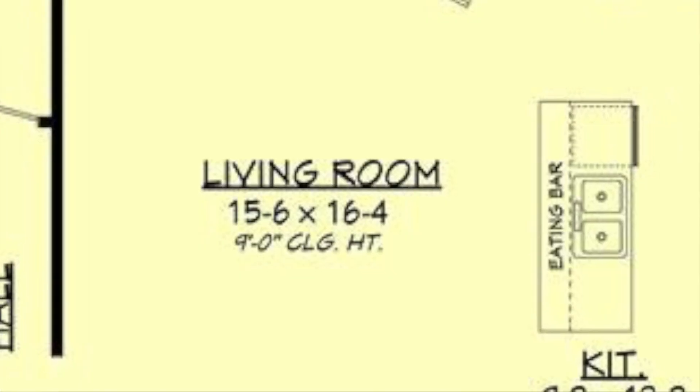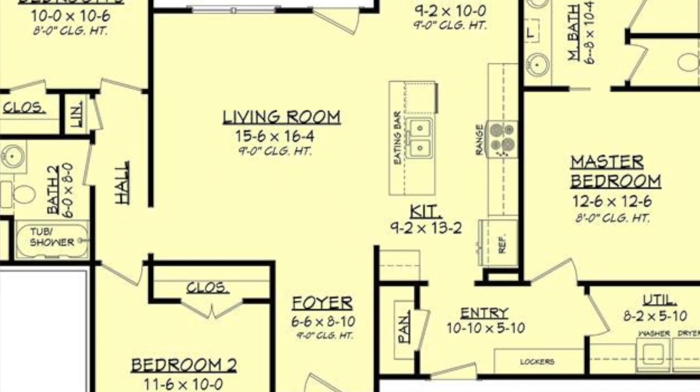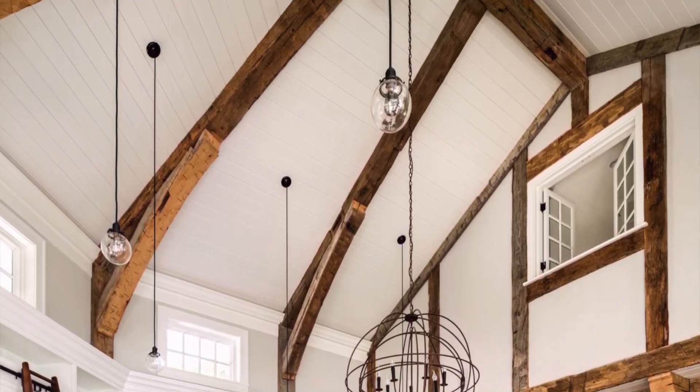The first thing is square footage of the home. Yes, that is taken into account — the bigger the home, the larger the system needs to be to heat and cool it. But in addition to square footage, you also have to take things into account like ceiling height. We're now talking about cubic footage — how much space is in that home that we actually have to heat and cool. We have customers with ceilings in certain rooms that are ginormous — vaulted ceilings that are 20 or 30 feet in the air — and all of that has to be taken into account.